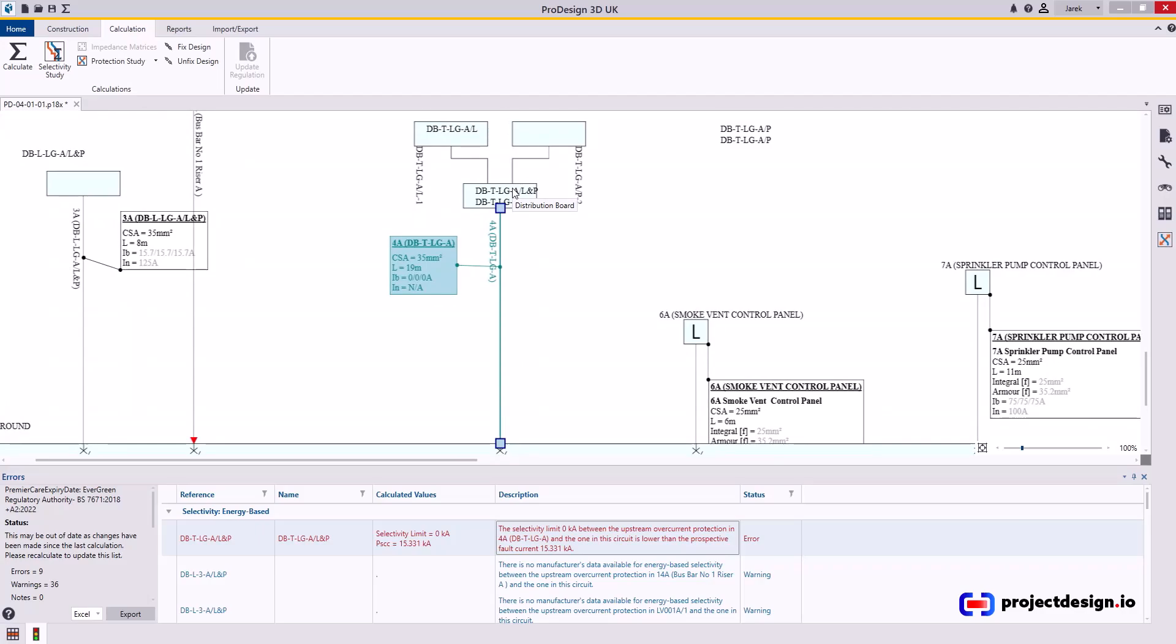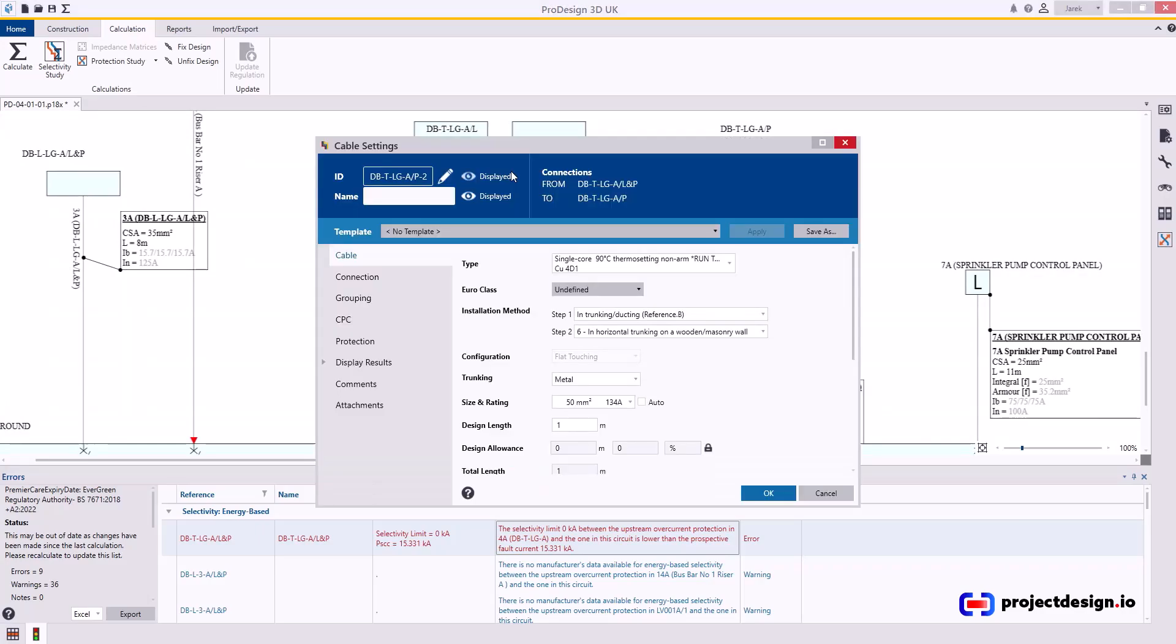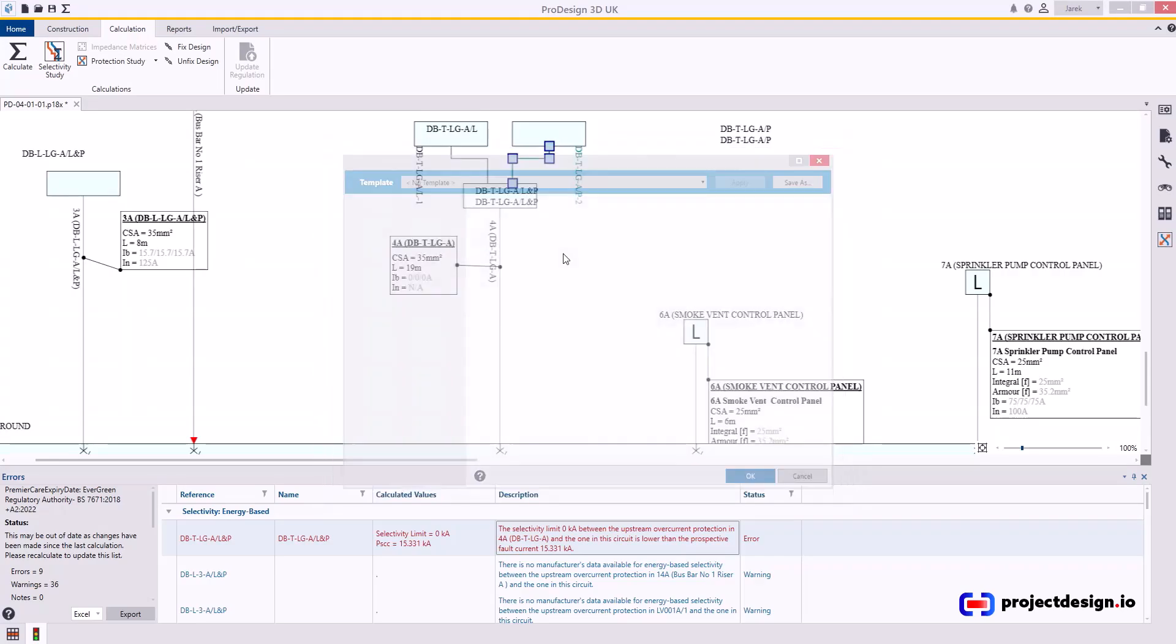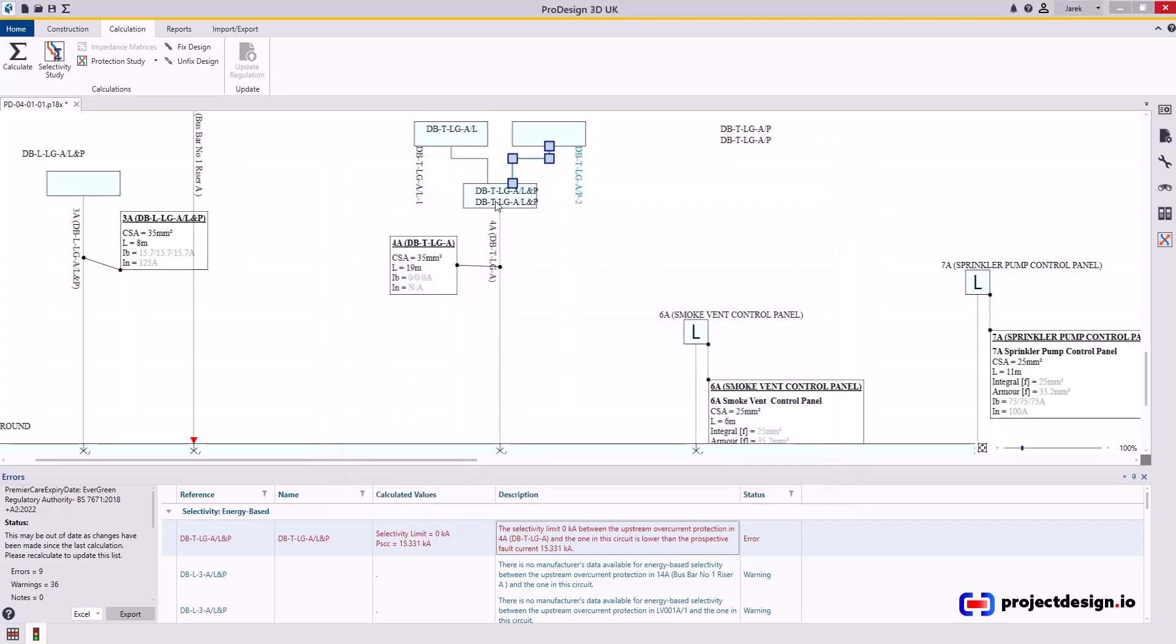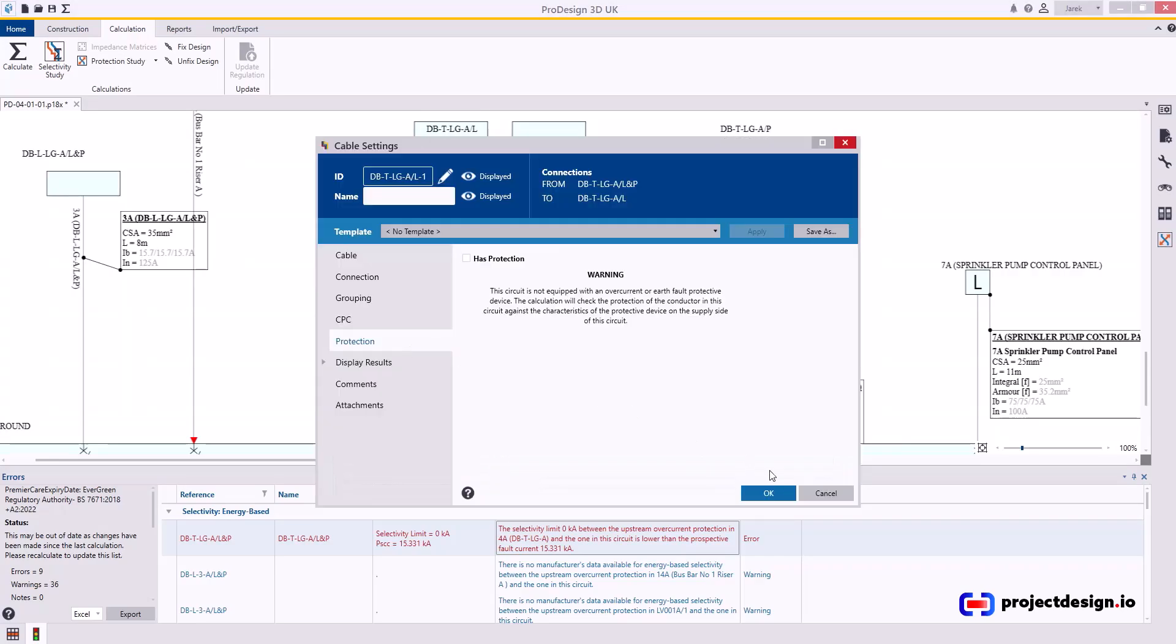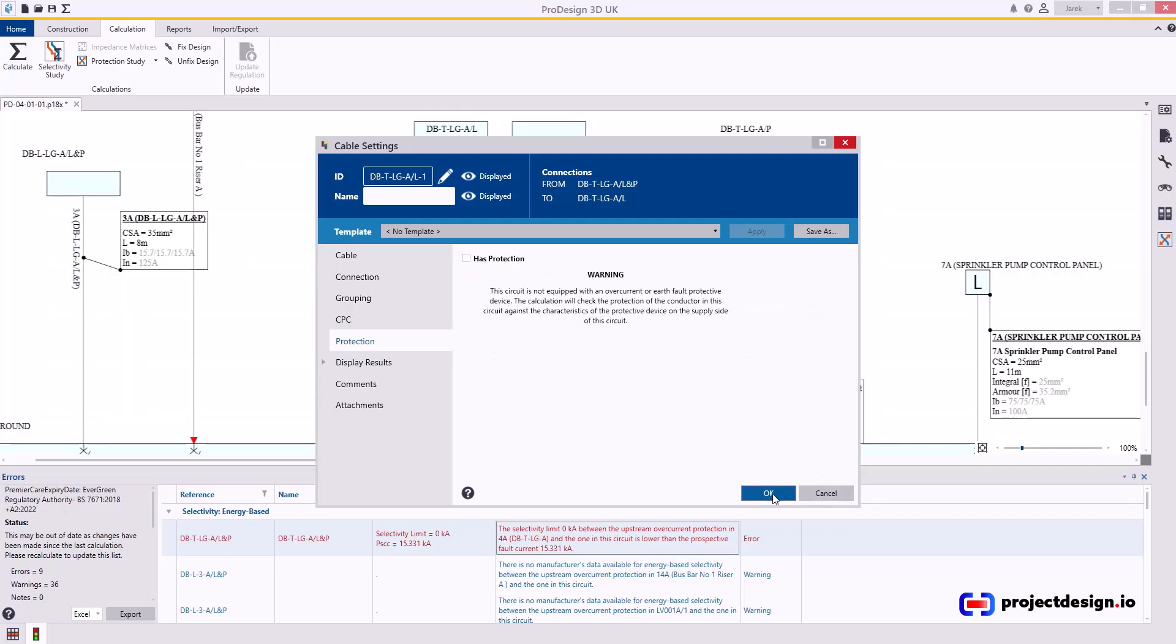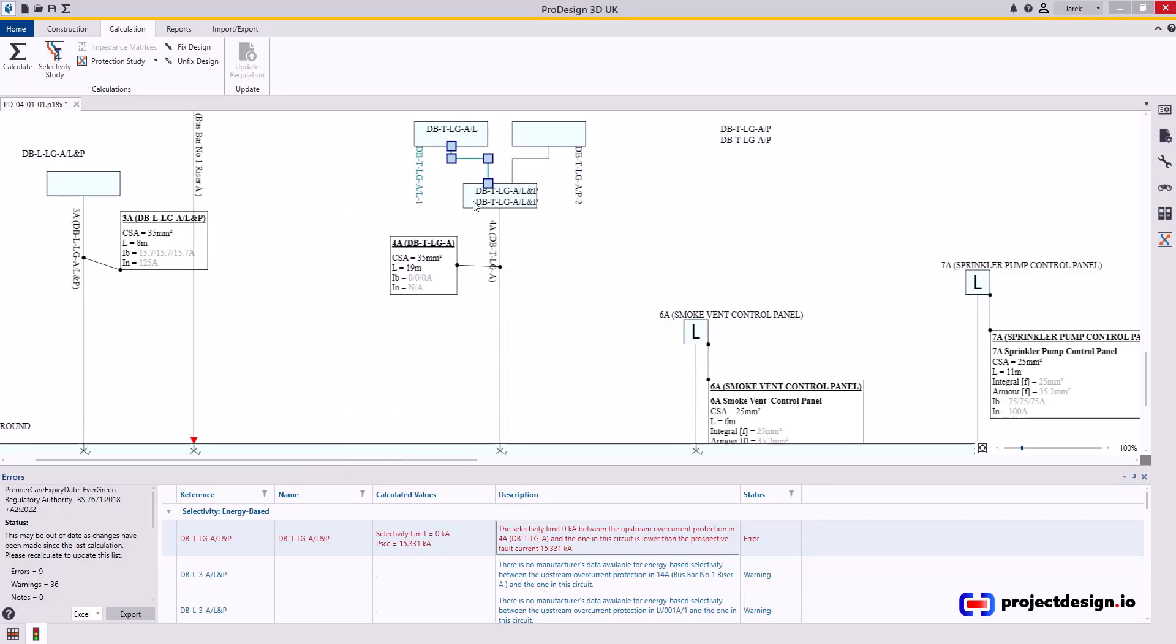That is a problem because you can't have discrimination, sorry, selectivity. You can't achieve energy-based selectivity or even time-current selectivity. You will not be able to achieve because you have two exactly the same devices in the upstream and at the incomer. Well, the problem here is in addition, those cables, I think they're also protected. No, they're not protected. So that's good.